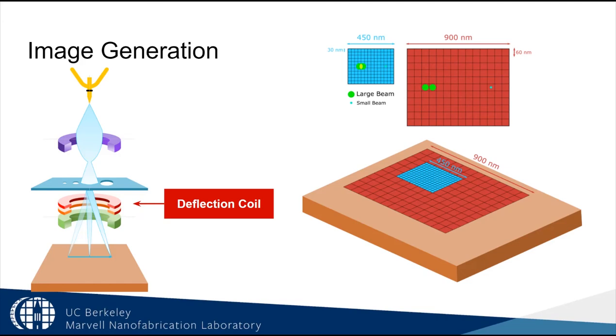Choose a working distance appropriate for the work you need to do, depending on how you need to balance resolution and depth of focus. In addition to controlling the SEM components, we also need to understand how magnification and astigmatism play a role in the resolution of our images. Up to now, the beam hasn't been moving. It's been stationary through the center of the beam column. In order to make an image, it has to be deflected.